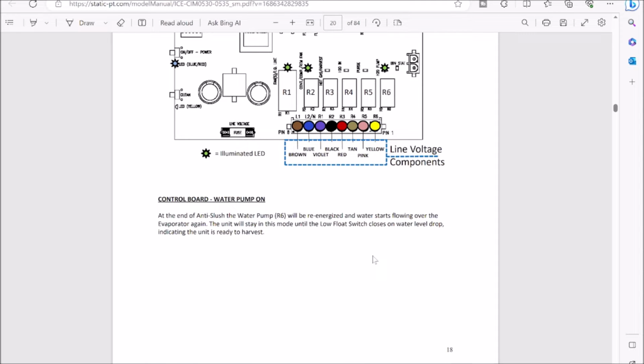Alright, so that error code is obviously not very specific. The one issue I'm finding with people troubleshooting ice machines is really the length of time they're spending on troubleshooting them. The ice machines are not easy to repair. I'll be the first to admit that. It took me time to understand them. But really, like I always explain, break things down into 3 circuits: water circuit, electrical circuit, and the refrigeration circuit. 90% of the time, it will not be the refrigeration circuit. And that's the hardest part to understand. So if we can eliminate that part of the circuit, the troubleshooting becomes a whole lot easier.